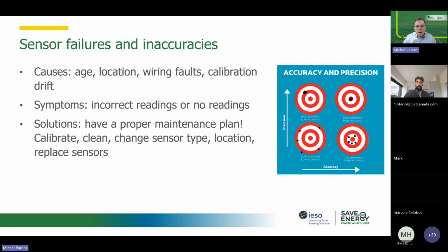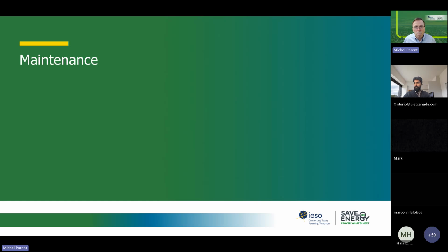There's a little graph here that I put in because a lot of people think that accuracy and precision mean the same things, and it's not. What we want on our BAS is some sensor that's very precise, because that's the one at the top here. Every arrow is in the same location, and then you can easily correct that. What we do in a BAS is put in a bias, and that brings that value to the proper value. So make sure that you have very precise sensors, and the accuracy can be corrected by calibration through bias.